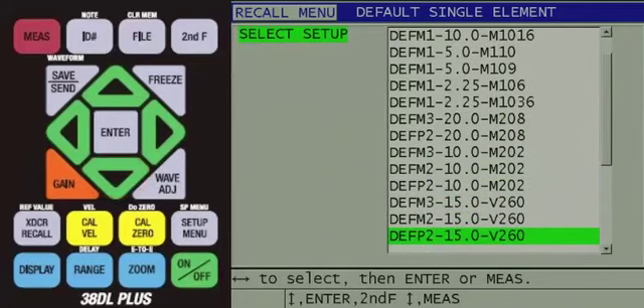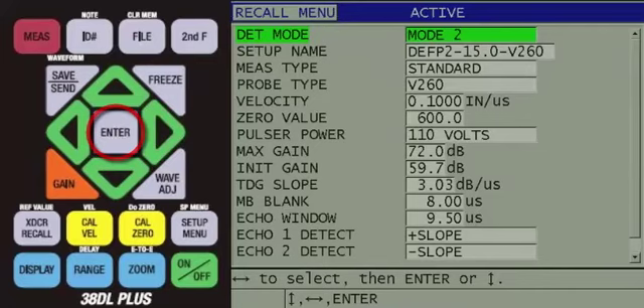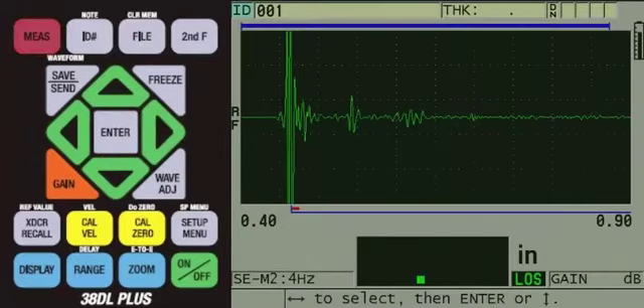So we will press the down arrow to highlight DEFP2-15.0-V260. At this point, you can press the red Measure key to recall the setup, or press the Enter key to see the parameters within the setup. If you press Enter, press the red Measure key next in order to recall the setup and return to the measurement screen. The default setup we recalled has a default sound velocity for plastic, so we do not need to change it at this time.